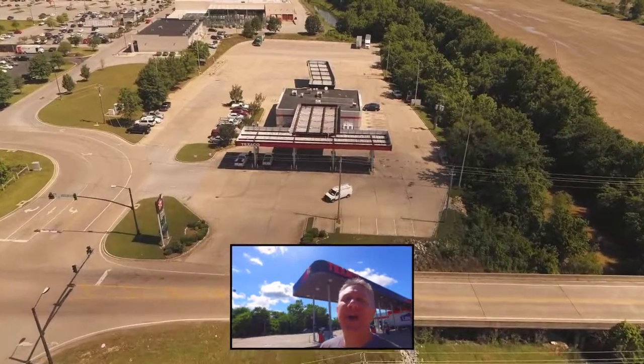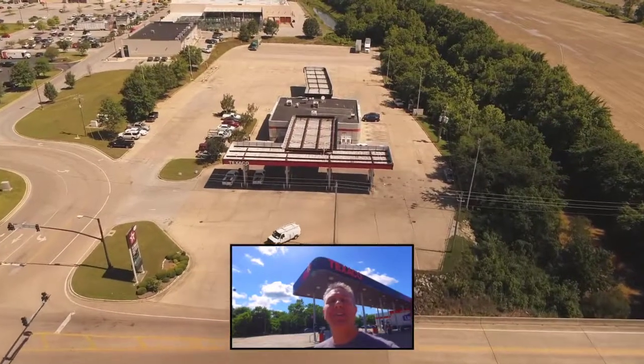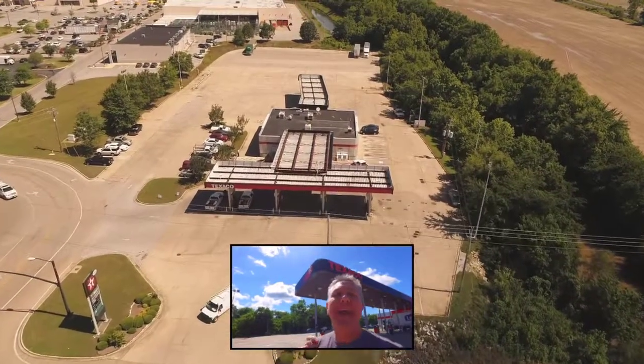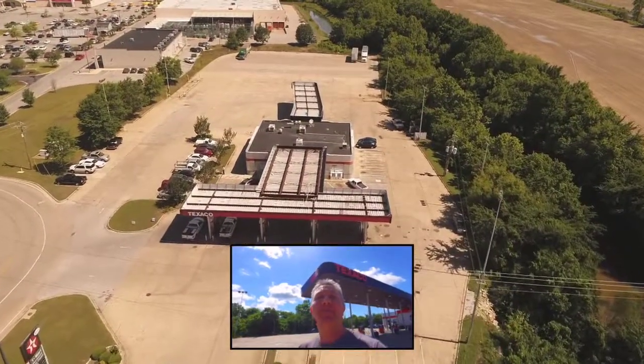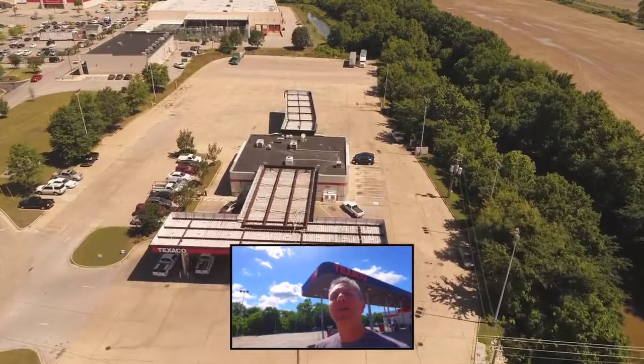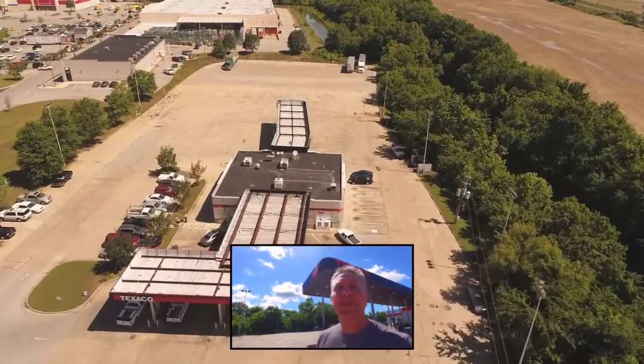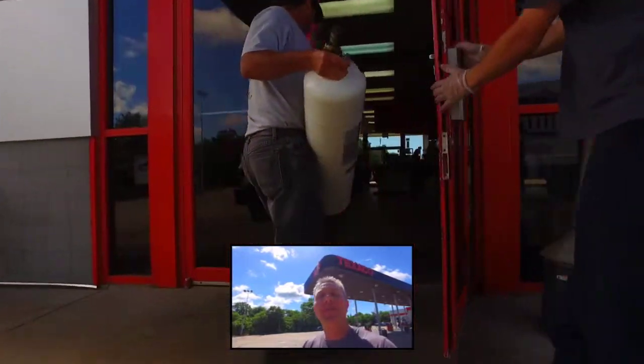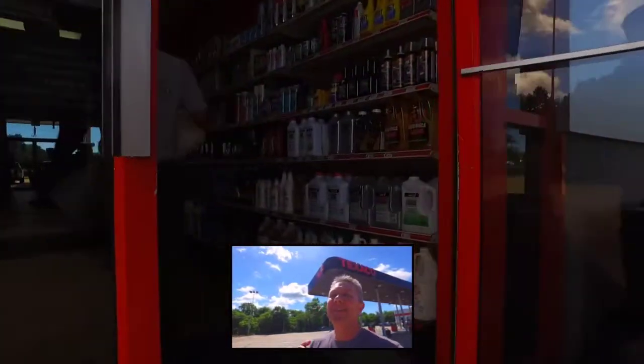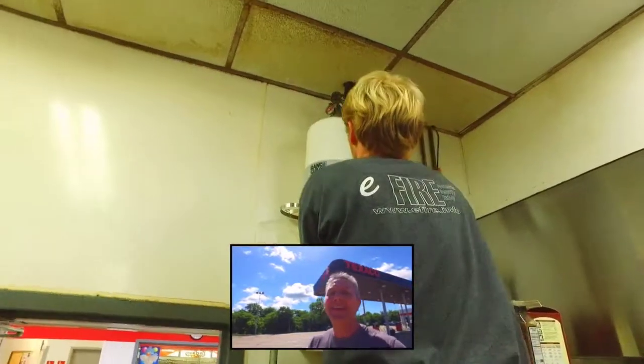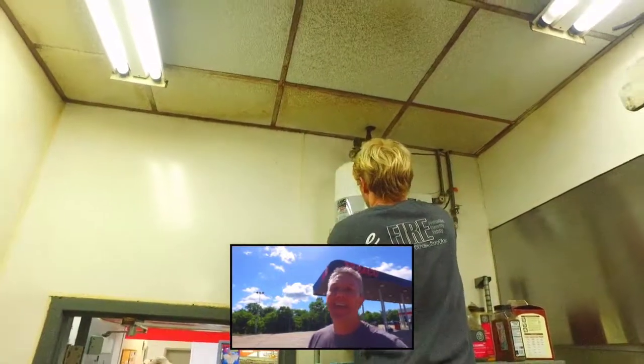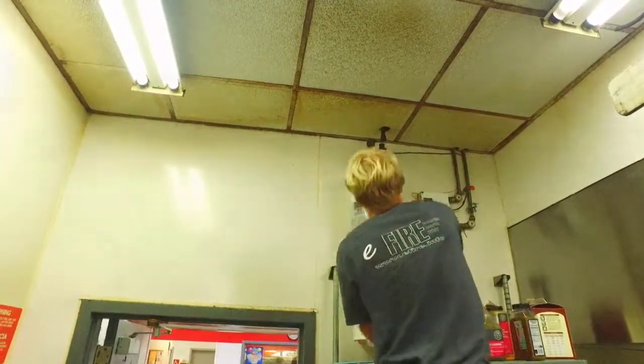Hey, this is David from E-Fire. We're at one of the Texaco locations in Tupelo, Mississippi. We're doing a hydrostatic test on the fire suppression system in the kitchen. So whether you own a restaurant, a convenience store, or a hotel, and you have a fire suppression system in the kitchen, it has to be inspected every 6 months, and it needs to be hydrostatically tested every 12 years.